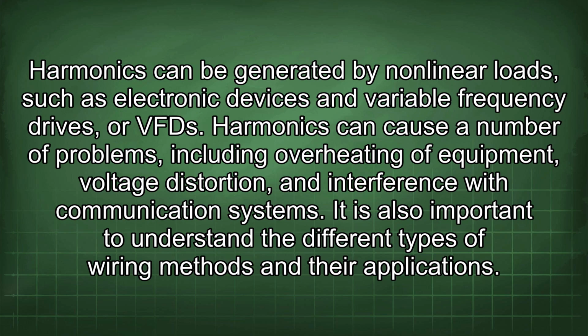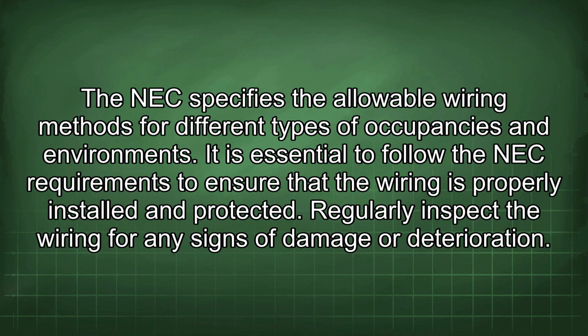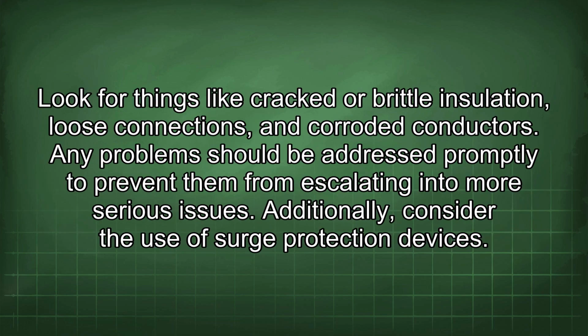It is also important to understand the different types of wiring methods and their applications. The NEC specifies the allowable wiring methods for different types of occupancies and environments. It is essential to follow the NEC requirements to ensure that the wiring is properly installed and protected. Regularly inspect the wiring for any signs of damage or deterioration. Look for things like cracked or brittle insulation, loose connections, and corroded conductors. Any problem should be addressed promptly to prevent them from escalating into more serious issues.